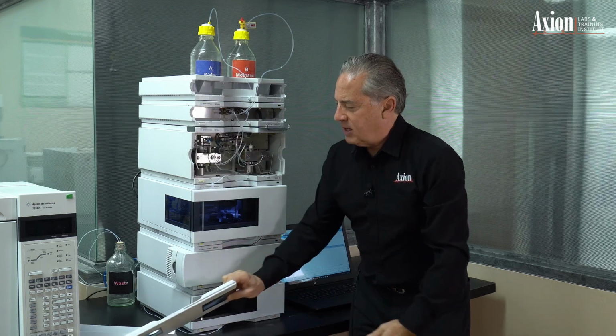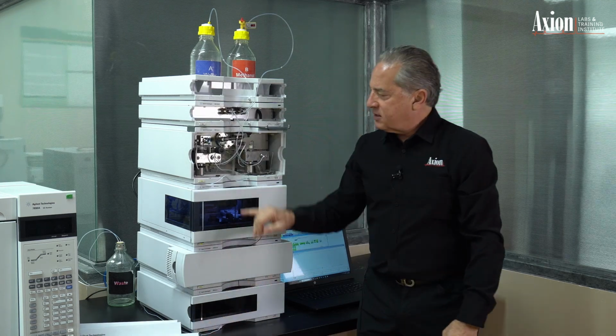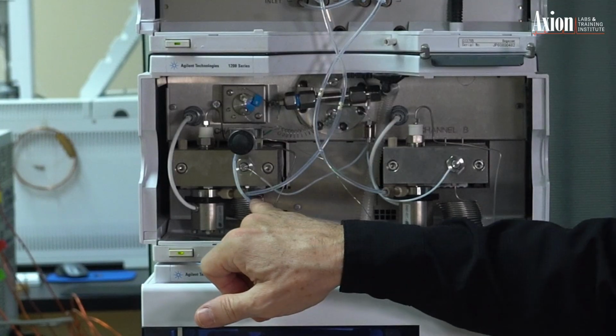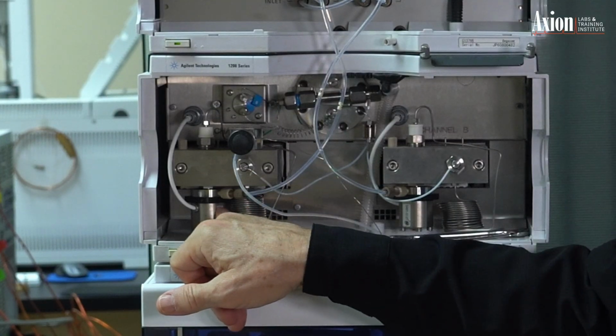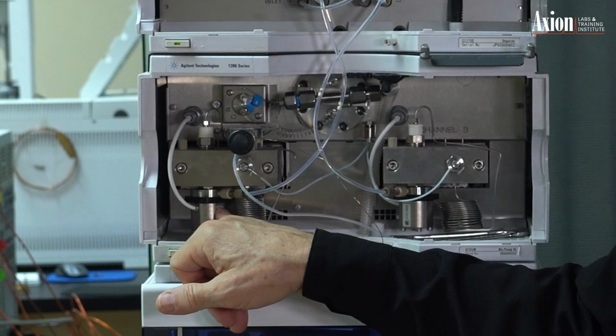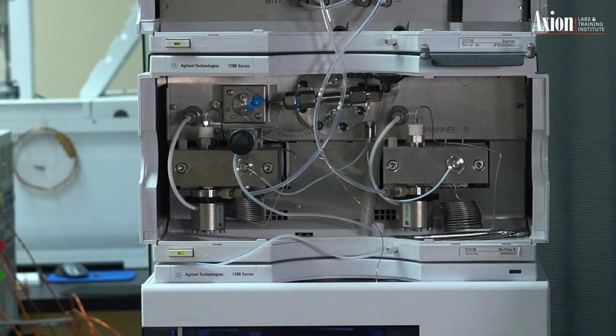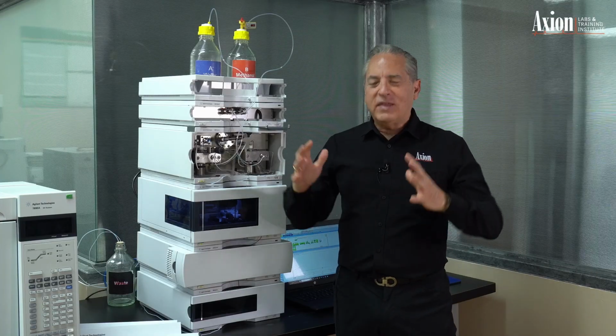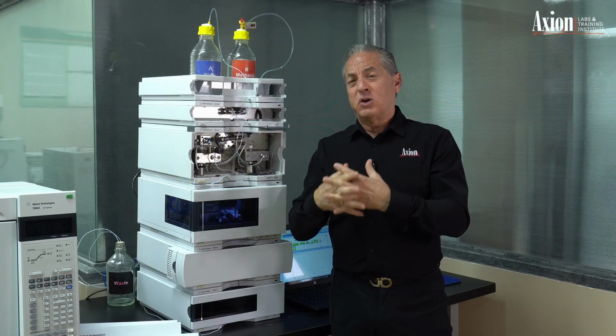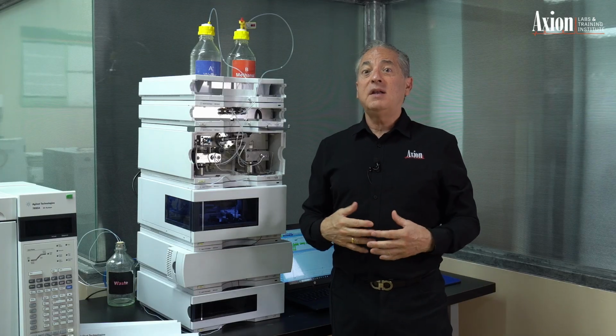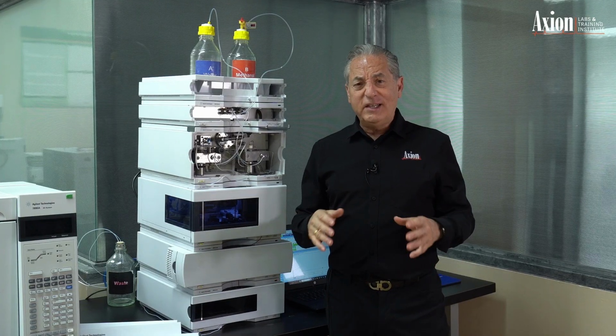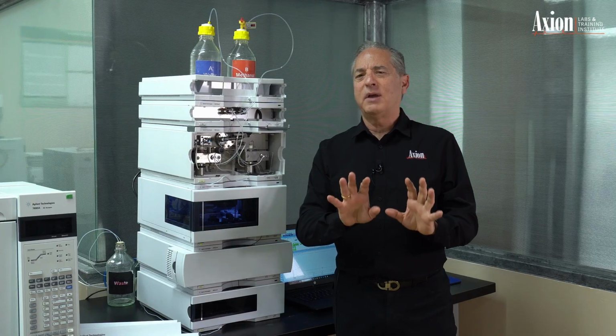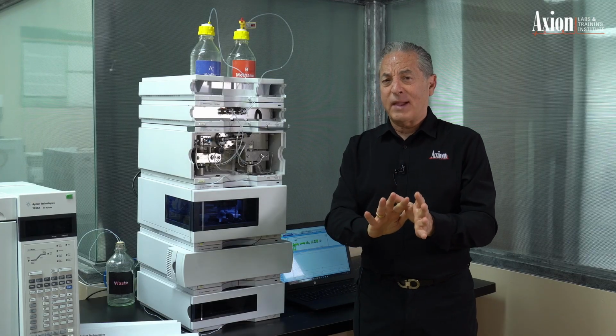So what happens is if your mobile phase is not degassed, as your pump draws in solvent right here into the inlet, it will then cause these bubbles to come out of solution, and a bubble drives your pump nuts. It doesn't know what to do with it. Bubbles are compressible, liquids are not. So bottom line is you never want to get a bubble in the pump. It's just going to give you a headache. You're going to spend a couple hours getting rid of it.